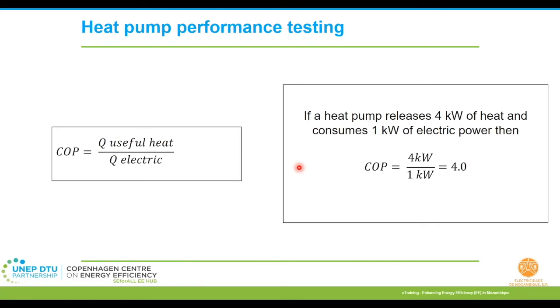And then you have heat pump performance. Basically, it is also measured in terms of COP. The indicators are given in terms of COP, the efficiencies. That is, if you say heat pump COP is 4, that means the heat pump releases about 4 kilowatt of useful heat for you by consuming about 1 kilowatt equivalent of electric power.